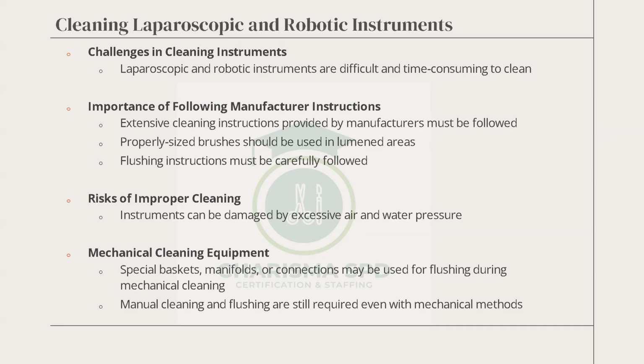The importance of following the manufacturer's instructions cannot be overemphasized here. If you don't follow them, like the jacket I'm telling you about, the same instrument has a jacket and it has a ratchet. You have to clean all the crevices. Take the jacket off, and then we disassemble the ratchet. Then after washing, you have to reassemble all that. That's where it's time consuming, but it has to come out clean. So you need properly sized brushes, as we said earlier, and you have to flush them, with flushing instructions as per the manufacturer's information for use, the IFU.